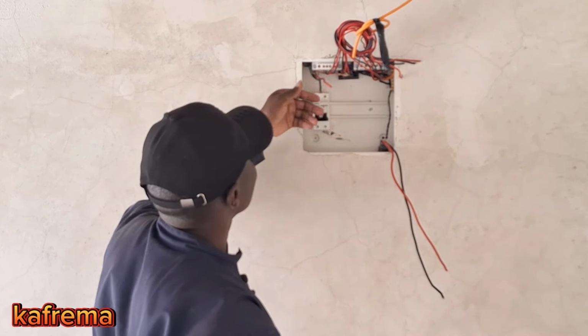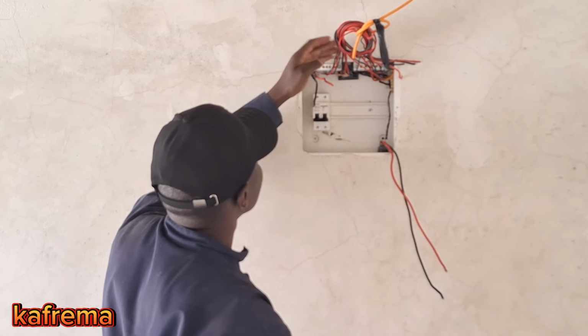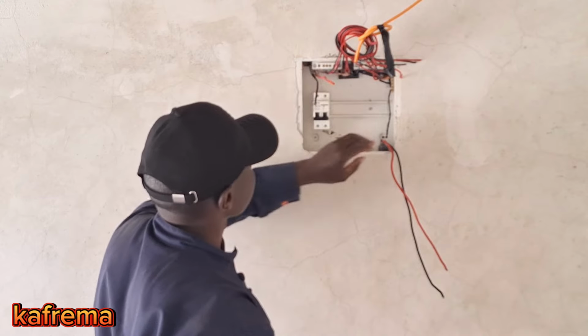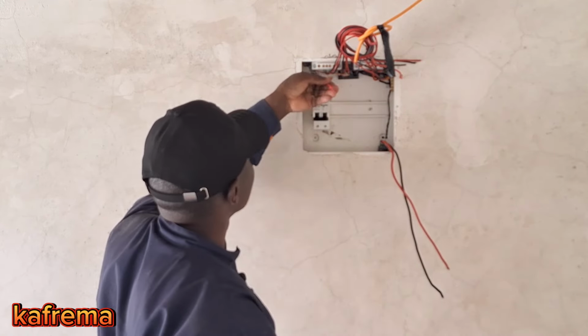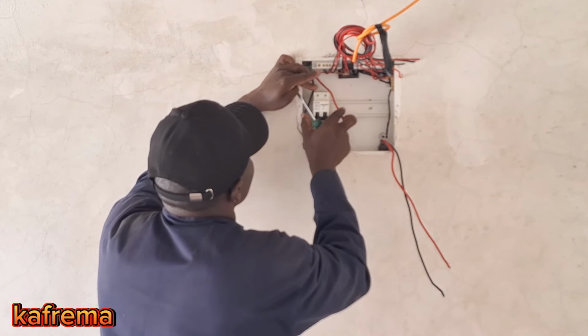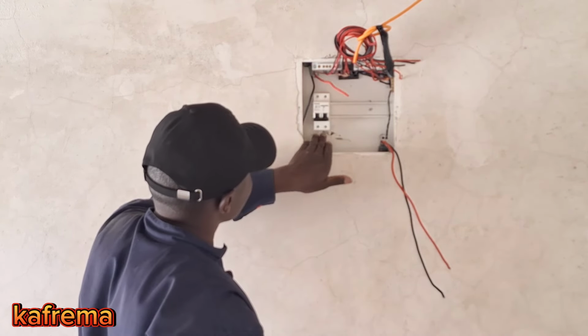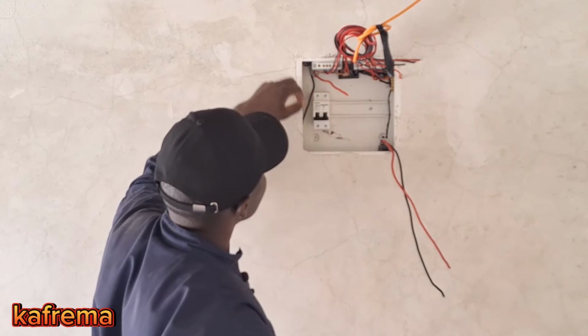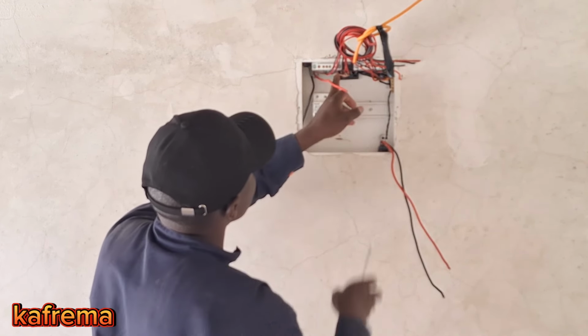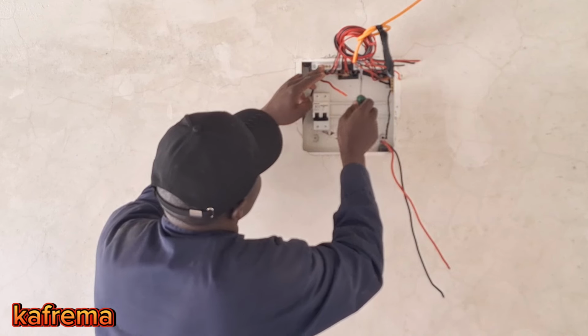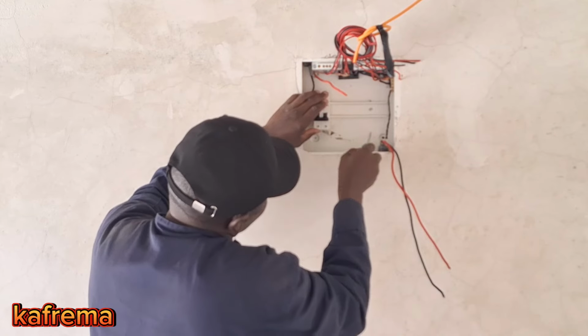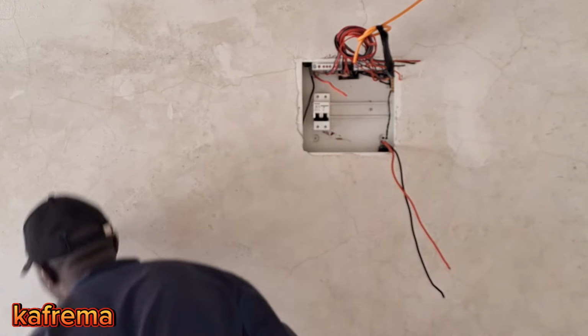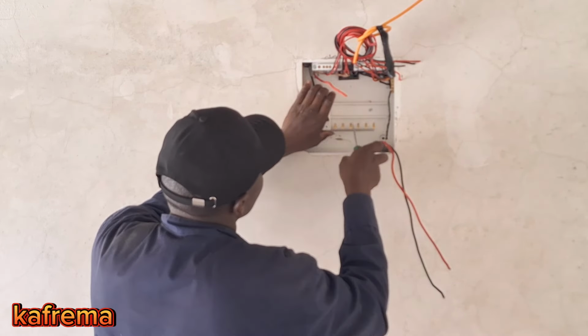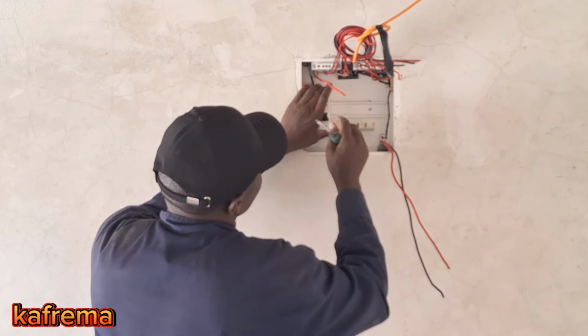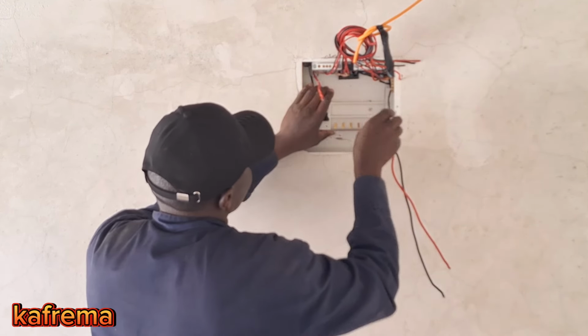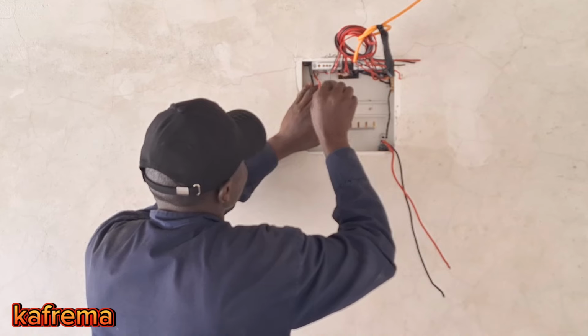This is the source from our power, and here above we have the neutrals. So this power will enter from above, will enter from here, then we'll get the neutral from this side of this point and take it here. All the neutrals will go here, then we'll join this neutral bar with this neutral bar, and the rest will go to this. Then all the lives will join the live from here and join with this bar here. This bar will go below and connect all the circuit breakers. This will power all the circuit breakers when it is switched on. So all the lives will go above, and all the neutrals will enter into these two bars.